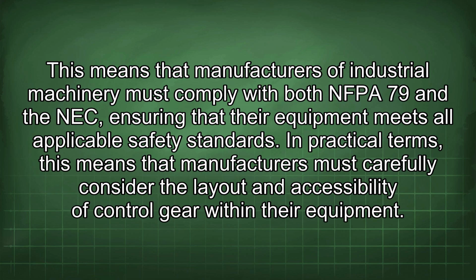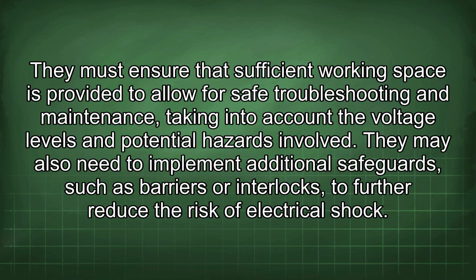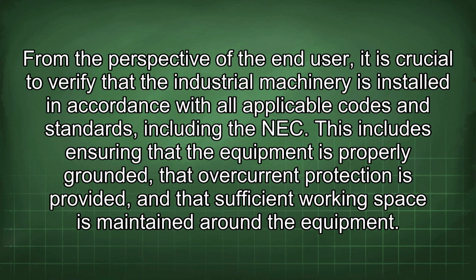In practical terms, this means that manufacturers must carefully consider the layout and accessibility of control gear within their equipment. They must ensure that sufficient working space is provided to allow for safe troubleshooting and maintenance, taking into account the voltage levels and potential hazards involved. They may also need to implement additional safeguards, such as barriers or interlocks, to further reduce the risk of electrical shock.